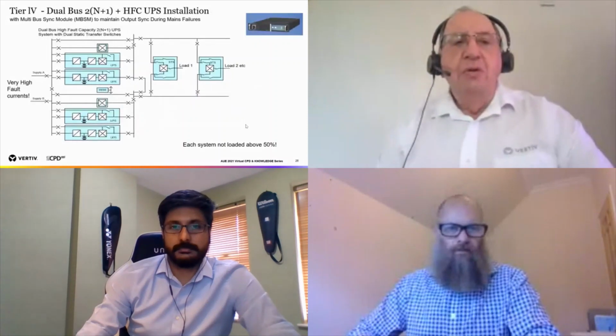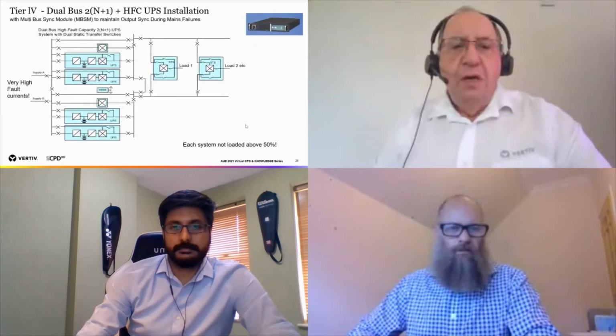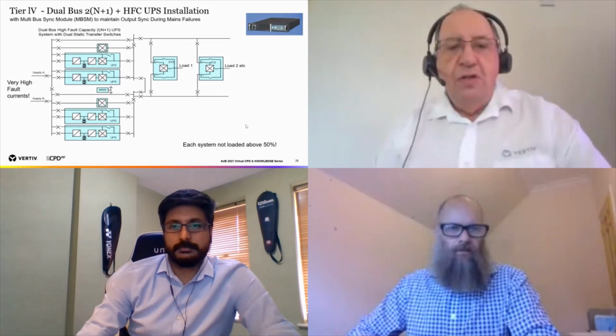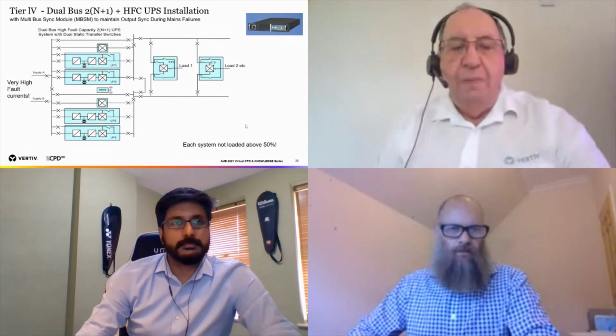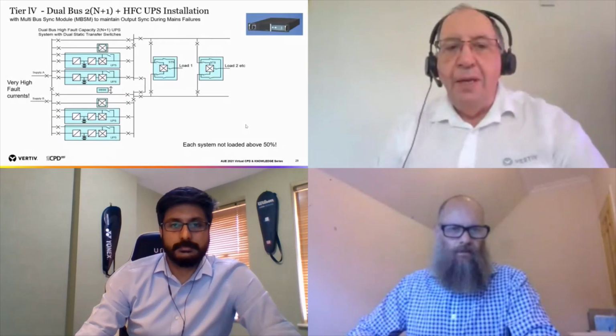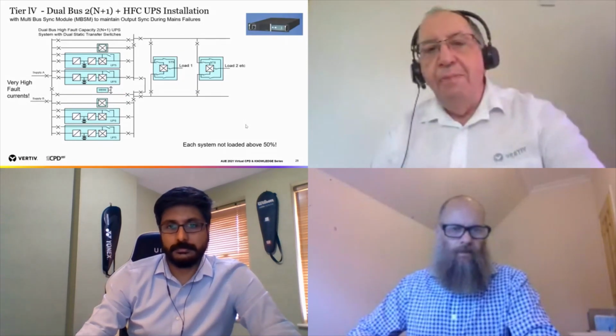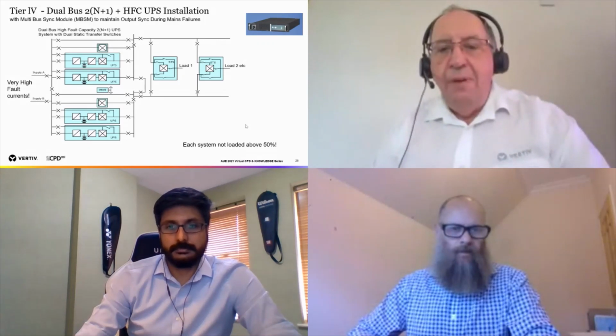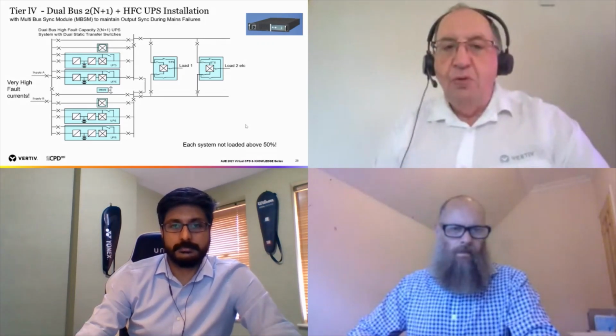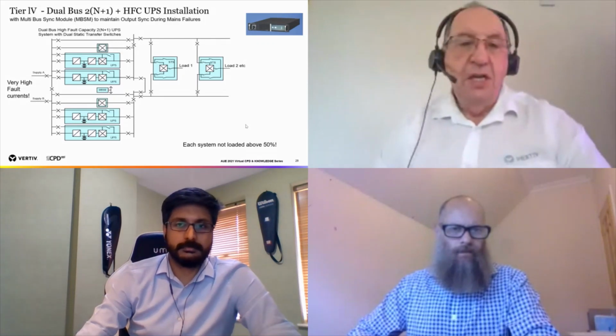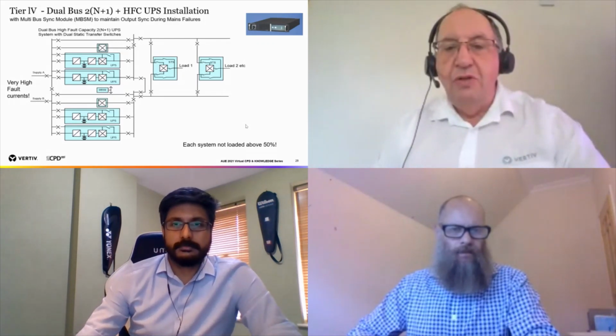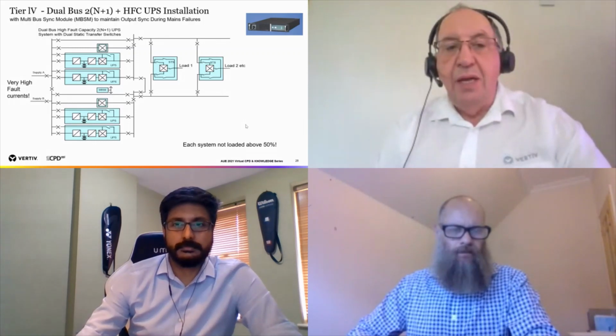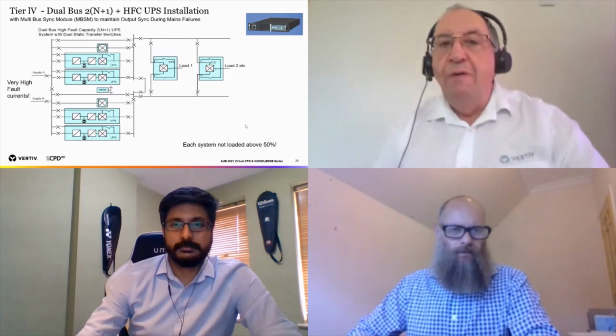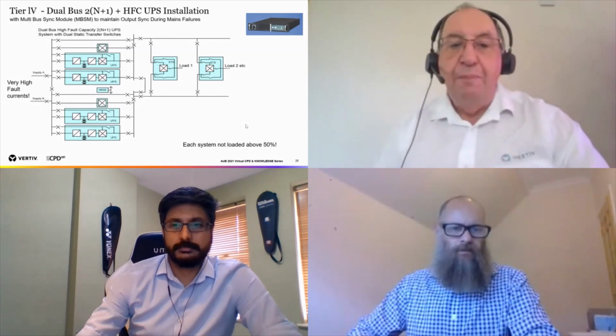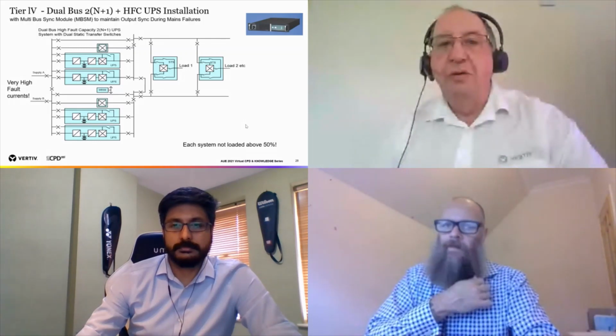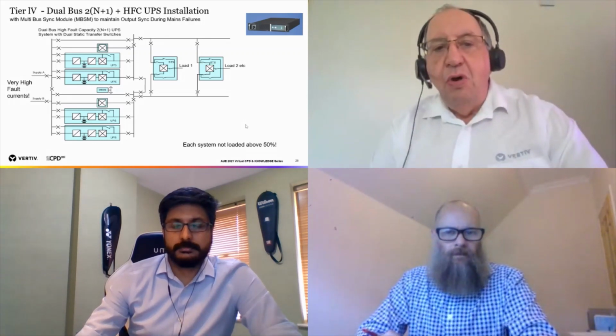So there we go to tier 4, and in tier 4 we've got dual supply UPSs on each side for A and B. We've still got the same maintainability downstream, but now this system is fault tolerant because it's in different places. We've got diverse routes going to the loads, and the A system and the B system do not go above 50%, because obviously if B fell over, A has to pick up the total load. So it's quite a comprehensive system.